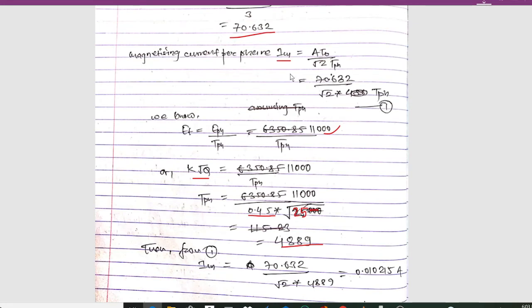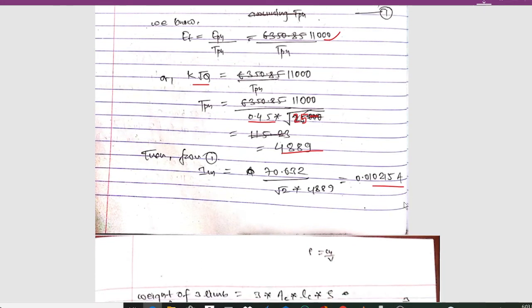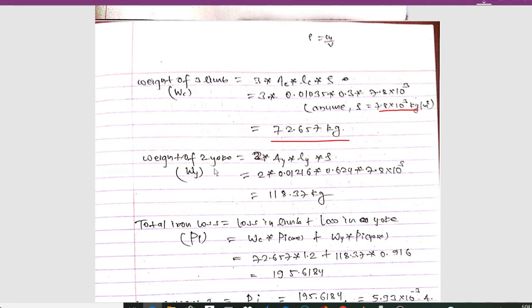Substituting AT_0 = 70.632 and TPS = 4889 into im = AT_0 / (root 2 × TPS), we get im = 0.010215 ampere. The weight of the limb is 3 × Ac × Lc × ρ = 3 × 0.01035 × 0.3 × 7.8×10³ = 72.657 kg. The weight of the yoke is 2 × Ay × Ly × ρ = 2 × 0.01216 × 0.624 × 7.8×10³ = 118.37 kg, using an assumed density of 7.8×10³ kg/m³.